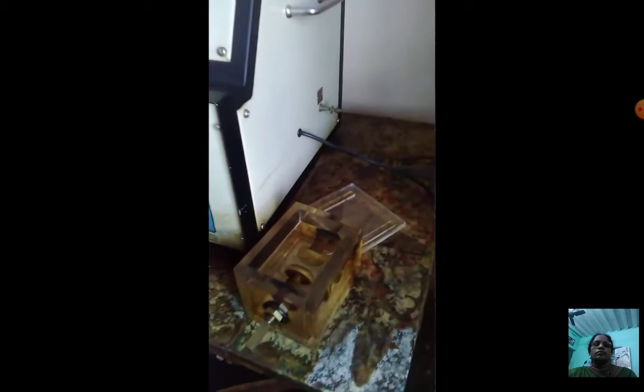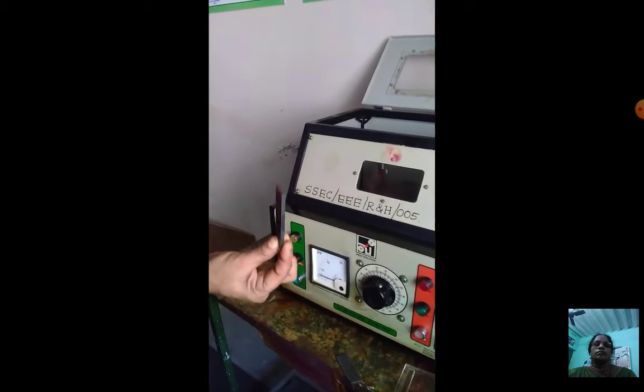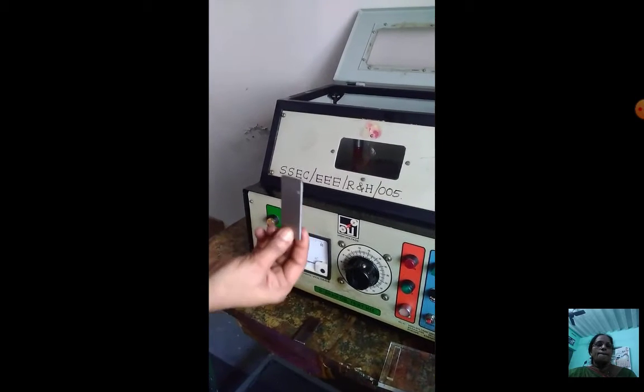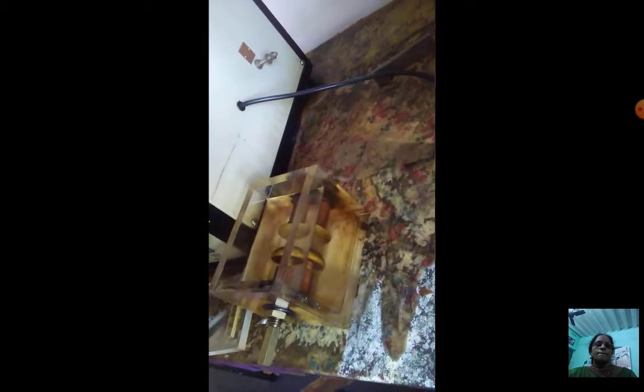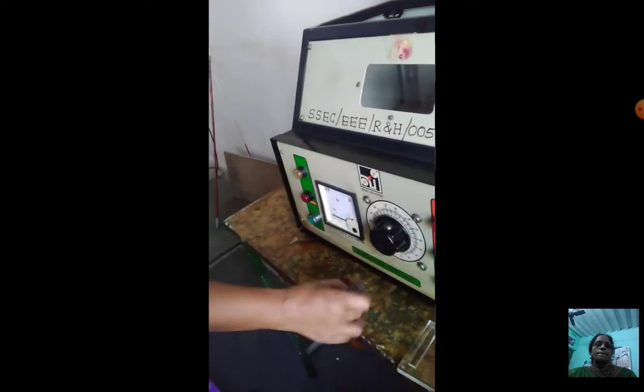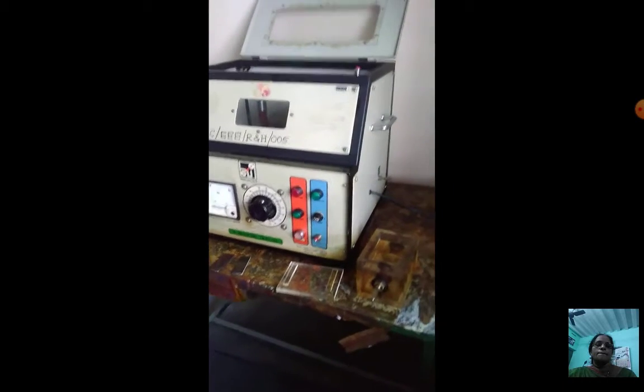You can see in the test cell, in between, two spear shaped electrodes are there. How you can adjust the gap in between: inside only, here you can adjust. So this is the top, that means the kit of this test cell. For gap measurement, this is the 4 centimeter gap, then this is the 3 centimeter gap. You can fix this in between the spear gap of the 2 electrodes. Now you can adjust this spear, and after that you will measure using this scale. You can know what the spear gap between the 2 electrodes is.